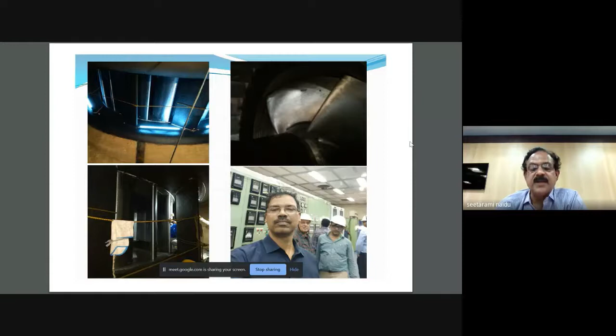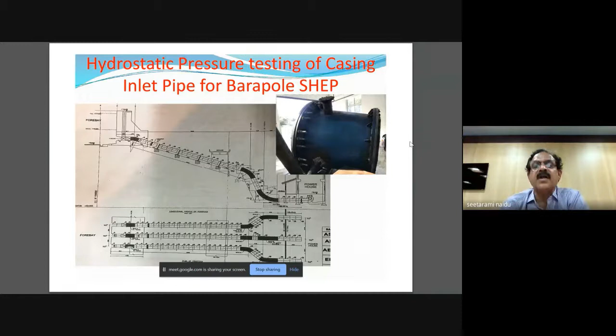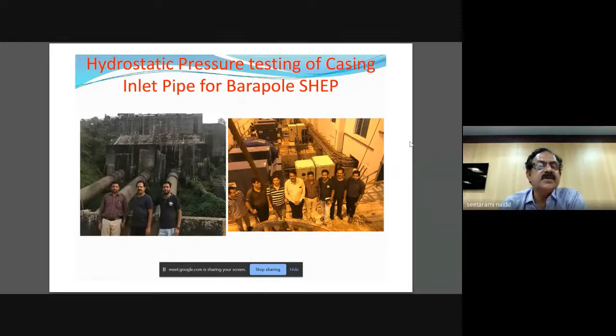This is the Barapole hydroelectric plant, Cannanore near Iriti. Recently, in January 2020, we carried out an investigation to ensure the performance of the inlet pipe for Barapole. It was tested, but this particular piece had failed, causing difficulty in operation. We then carried out inspection and actual hydraulic testing of the power plant, and now it is working properly after modification of the casing inlet pipe. This is the testing team and their operation, and this is the construction, how it looks.